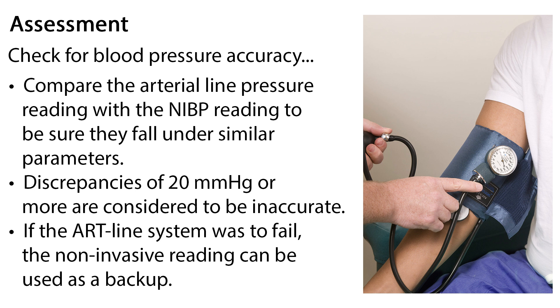To continue your assessment, check for blood pressure accuracy by comparing the arterial line pressure reading with the non-invasive blood pressure reading to be sure they fall under similar parameters. Discrepancies of 20 mmHg or more are considered inaccurate. If the art line system were to fail, the non-invasive reading can be used as a backup.